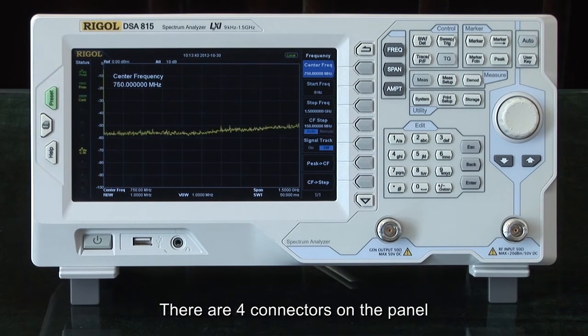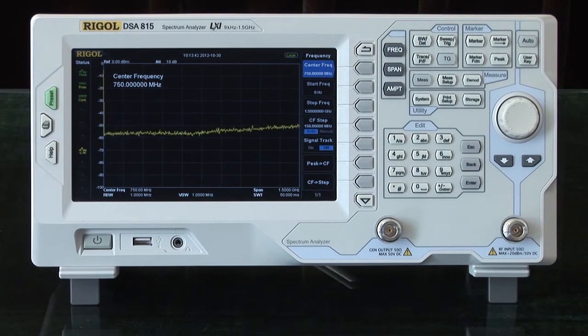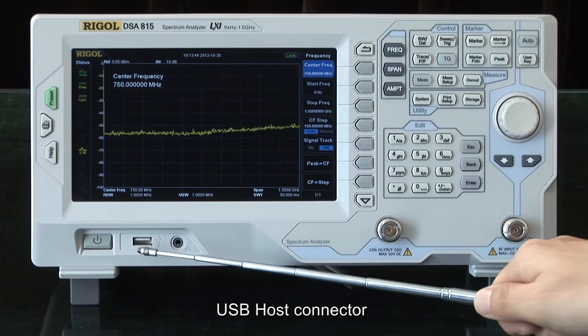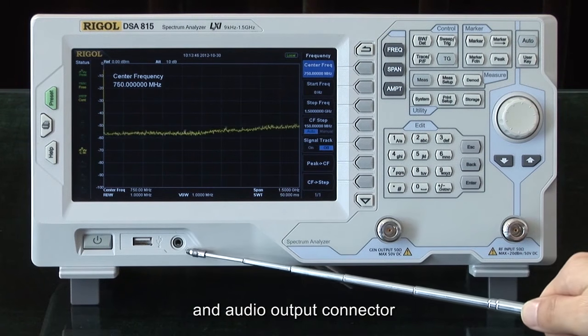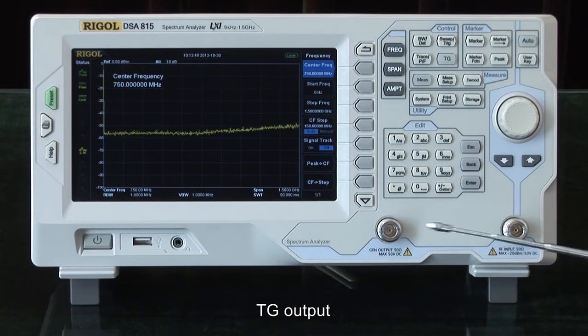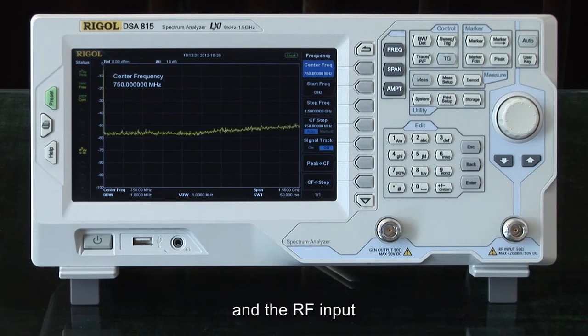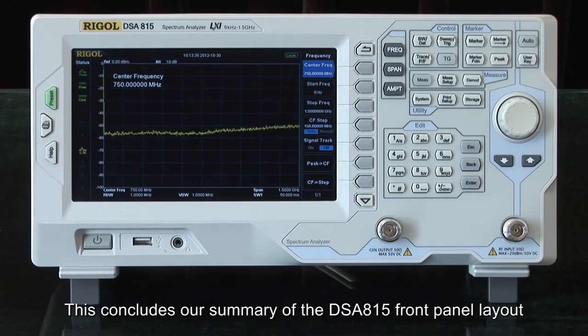There are 4 connectors on the front panel: a USB host connector, an audio output connector, a tracking generator output if that option is available, and the RF input. This concludes our summary of the DSA815 front panel layout.